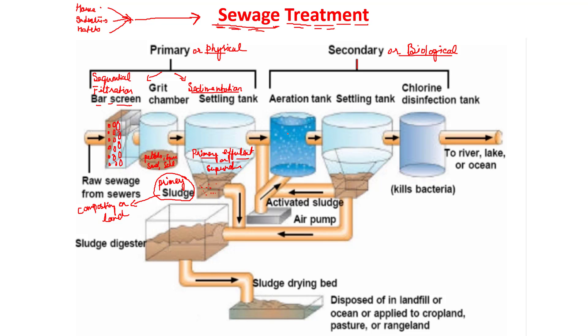In biological treatment, the primary effluent is pumped into aeration tanks. Aerobic microbes — aerobic bacteria and fungi — are present, and air is pumped into this aeration tank to allow vigorous growth. Through this vigorous growth of bacteria and fungi, they form a mesh-like structure known as flocs, which are formed by fungal filaments and bacterial cells.